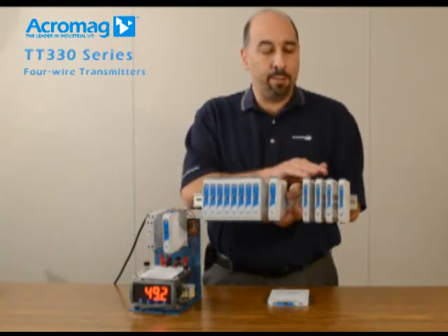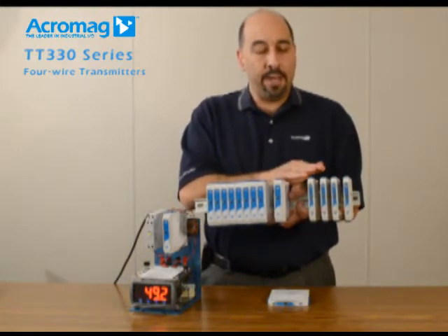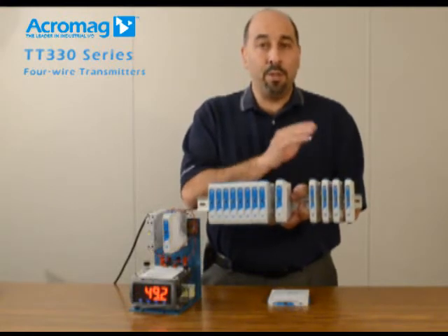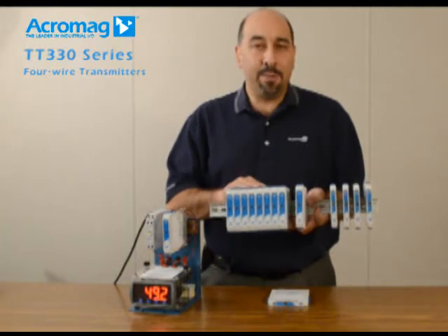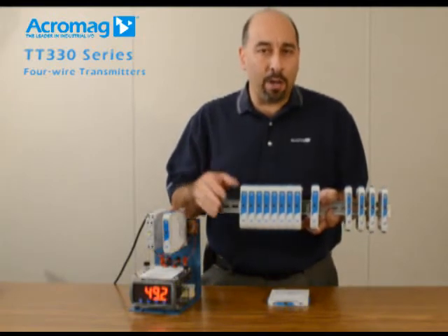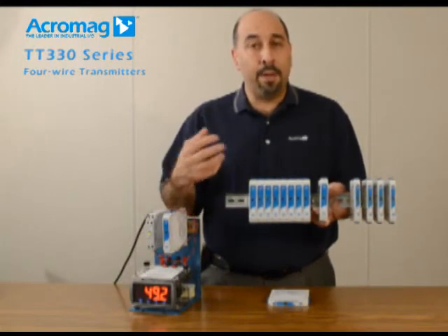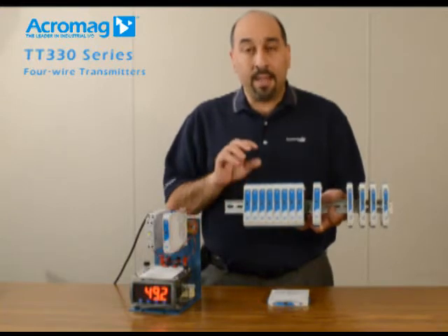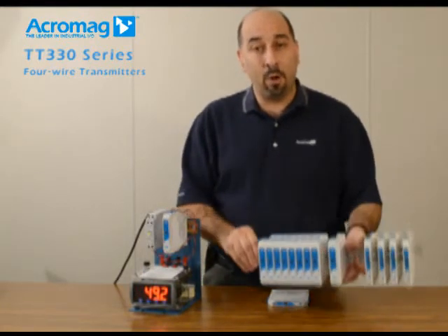You might already be familiar with Acromag's TT-230 series line, which is a true two-wire transmitter, DIN rail mount signal conditioner with a universal 4 to 20 milliamp output sink or source. The TT-330 series line is a true four-wire transmitter that includes a separate power source, an isolated input, and an isolated output. So by definition it's a four-wire transmitter. This line has a lot of extra features that the TT-230 series does not. I'd like to give you a quick overview.